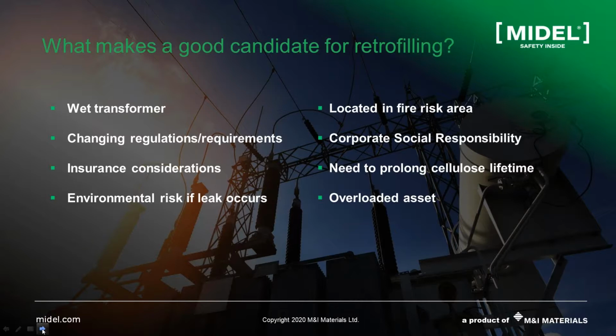So think about your own transformers, and are any of these scenarios familiar? Do you have transformers that are wet and continually need drying operations carrying out as their breakdown voltage falls below the required minimum? Does your substation or transformer installation still comply with regulation and guidance? The built environment around the transformers may have evolved since it was commissioned and requirements become more stringent. What options do you have available? Has a recent audit or inspection taken place in which a mineral oil transformer is considered too risky and recommendations put forward to introduce a K-class fluid such as MIDEL? In this case, retrofill would be the most cost-effective way of reducing that risk.